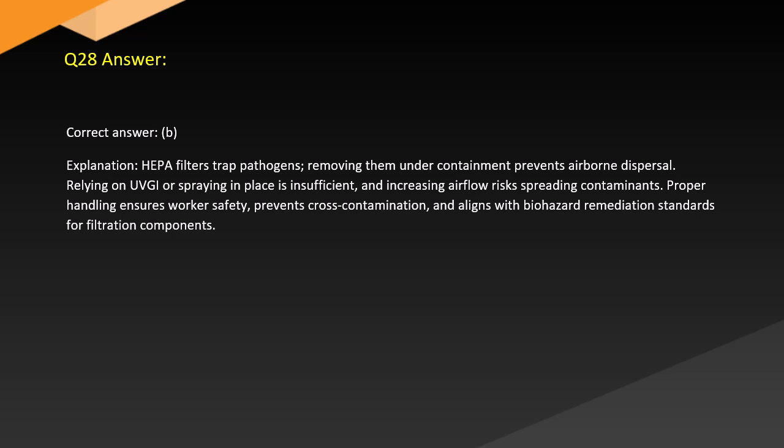Answer. Correct answer, B. Explanation. HEPA filters trap pathogens. Removing them under containment prevents airborne dispersal. Relying on UVGI or spraying in place is insufficient, and increasing airflow risks spreading contaminants. Proper handling ensures worker safety, prevents cross-contamination, and aligns with biohazard remediation standards for filtration components.